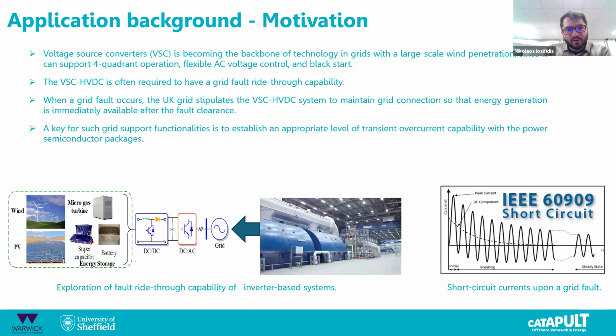Next, please. In any grid, the voltage source converter is becoming the backbone technology. It keeps increasing in grids that have large penetration of wind or other renewables. It gives flexible operation and has 4-quadrant operation. It is also required to have grid fault ride-through capability, meaning that according to the UK grid standards, they need to maintain grid connections so the power generation is immediately available after the fault clearance. So the key to this grid fault capability is to establish an appropriate level of transient overcurrent capability. Can you go to the next slide, please?